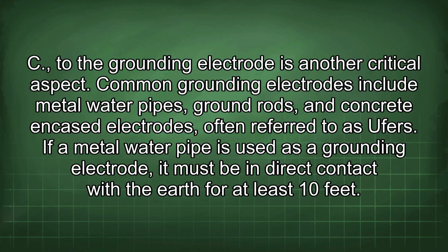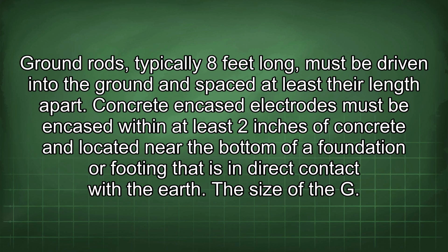If a metal water pipe is used as a grounding electrode, it must be in direct contact with the earth for at least 10 feet. Ground rods, typically 8 feet long, must be driven into the ground and spaced at least their length apart. Concrete encased electrodes must be encased within at least 2 inches of concrete and located near the bottom of a foundation or footing that is in direct contact with the earth.